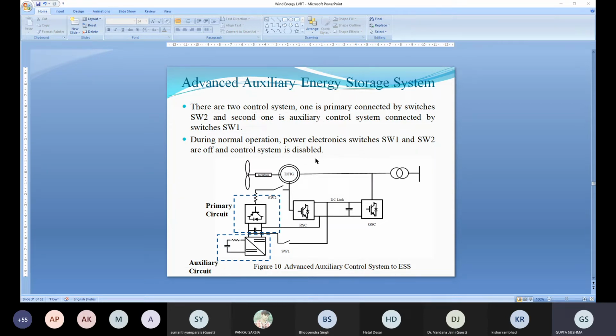But at the time of fault, there are two cases, fault and disturbance. At the time of fault, when there is a large rotor current and large DC link voltage, at that time this primary circuit will disconnect, and this auxiliary circuit will connect through the S2 switch. And when there is an over voltage over here, this energy is transferred to this battery. So it can operate under normal disturbance as well as in fault condition.